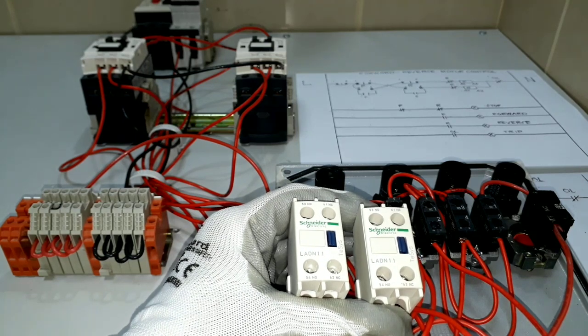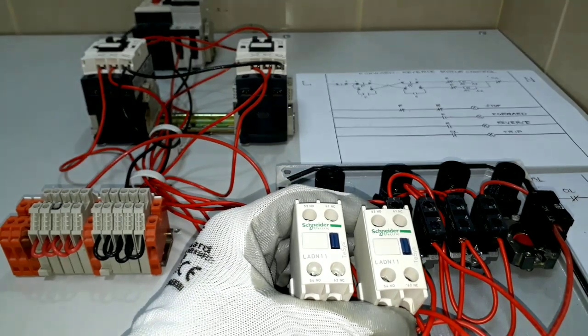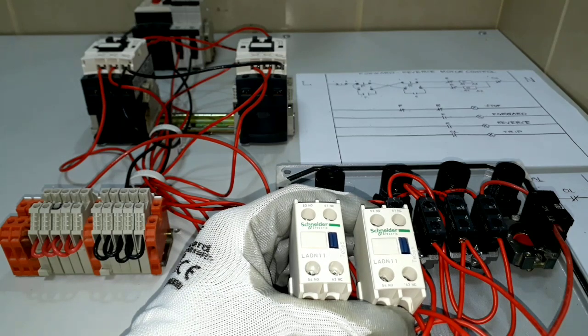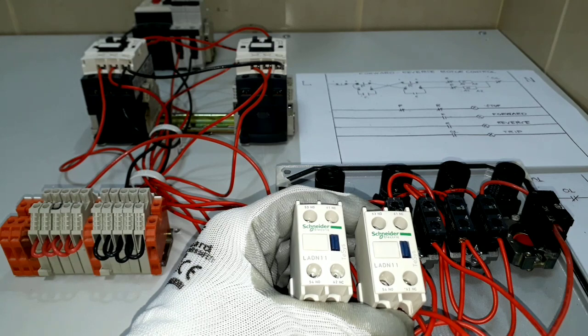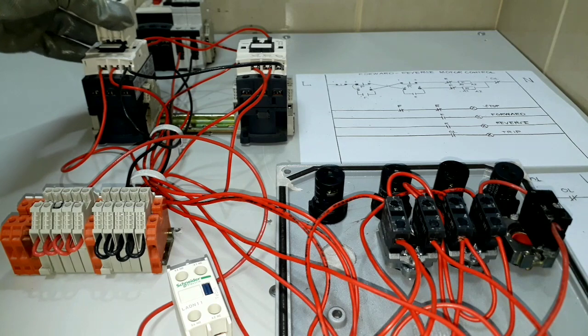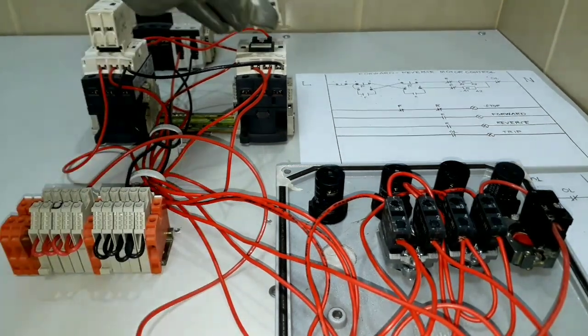Before we proceed on our wiring tutorial for activating our pilot lamps for stop, forward, reverse, and trip, I will show you that we will be needing two pieces of auxiliary contact block, model number LADN11 from Schneider. This is a combination of a normally closed contact and a normally open contact. We will fix one on our forward contactor and the other one on our reverse contactor.